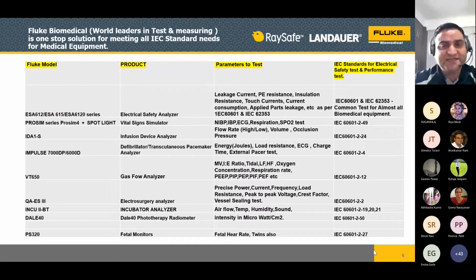Now, in the same way, with vital sign simulators you can test a DUT with NIBP, IBP, ECG, respiration, SpO2. And on the extreme right, the column which I have mentioned, those are the standards. Suppose somebody wants to do patient monitor testing, he has to follow IEC 60601-1, or 62353 for the electrical safety part. And for the performance part, he has to follow IEC 60601-2-49. So those are the performance standards.